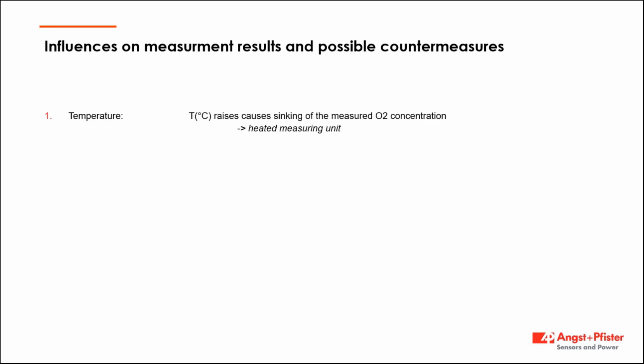First of all, we have the temperature. Our sensor is temperatured to 55 degrees, to make sure that the temperature influence from outside is minimized. Why does temperature have an influence? It's a physical phenomenon: if you have the oxygen molecules in between those pole shoes, and you have a higher temperature, those molecules will be spread all over the measuring cell.